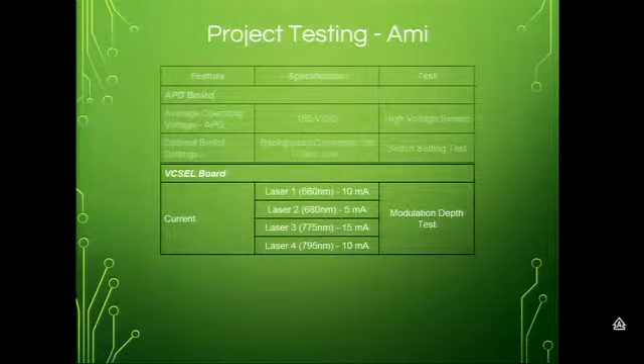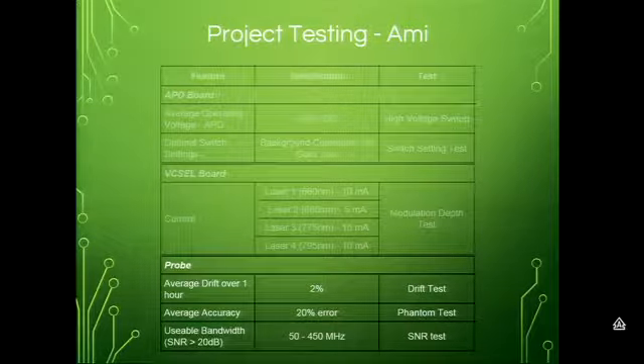So for our VCSEL board, we had to find what currents we wanted to run the different wavelengths at, and we found them to be 10, 5, 15, and 10 milliamps, and we used a modulation depth test for that. And then for the probe as a whole, we measured the average drift over 1 hour, so we took a measurement at the first minute, and then we kept taking it for 60 minutes. And we found that the deviation from that first measurement only went to 2%, so it was pretty constant.